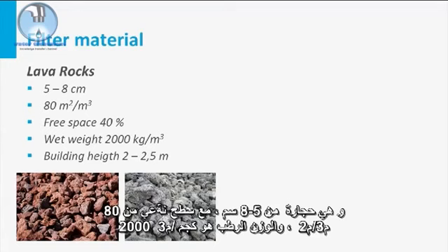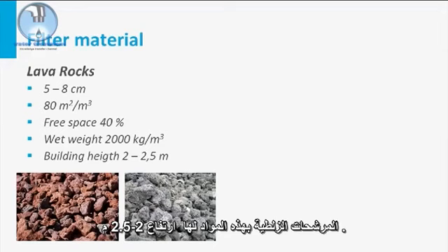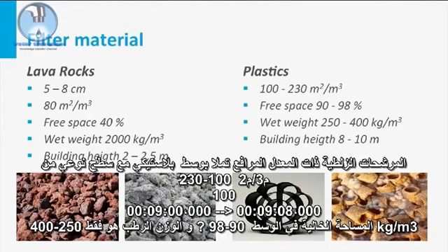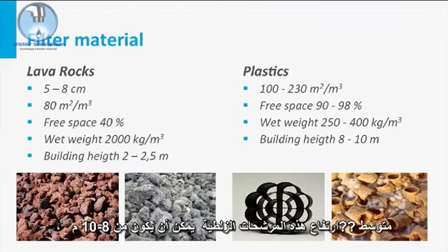Traditionally, lava rocks are used. These are 5 to 8 cm stones with a specific surface of 80 square meters per cubic meter. The wet weight is 2000 kg per cubic meter and the free space in the bed is about 40%. Trickling filters with this filling material have a height of 2 to 2.5 meters. High-rate trickling filters are filled with plastic with a specific surface of 100 to 230 square meters per cubic meter. The free space in the bed is 90 to 98% and the wet weight is only 250 to 400 kg per cubic meter, so the average height of such a trickling filter can be 8 to 10 meters.